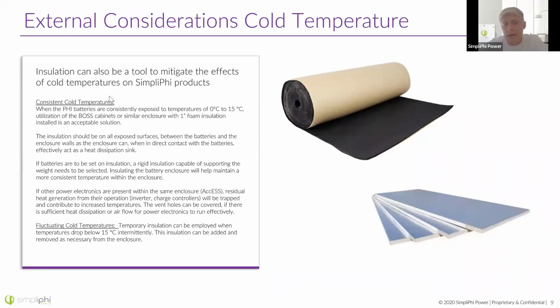Here's what we'd recommend: if you're putting the batteries inside one of our metal cabinets, use a rigid foam insulation. This foam insulation has to support the weight of the batteries, because if you compress the insulation, all the air trapped within it is gone, and the insulating value is greatly lessened. A rigid foam board will hold the weight of the batteries, prevent them from pushing all their heat out through the metal cabinet of the BOSS enclosure or AccESS enclosure, and help keep the internal temperature of the cabinet up.